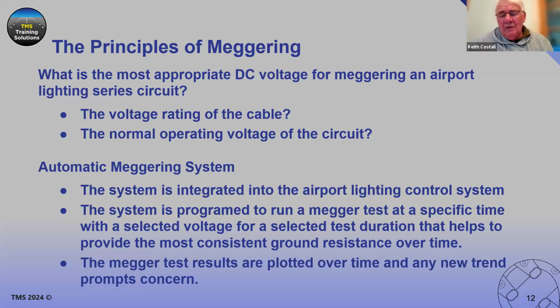Yeah. There are different viewpoints all over the globe, really, on this. And whilst the standards, in accordance with the ICAO Aerodrome Design Manual Part 5, state quite clearly that, based upon the 1 microamp, 2 microamp rule associated with cable and the isolating transformers, then we can calculate what the minimum acceptable insulation resistance values are, it's based upon 5,000 volts. So, using Ohm's law, as you mentioned earlier, we can calculate what the minimum acceptable insulation resistance value is.